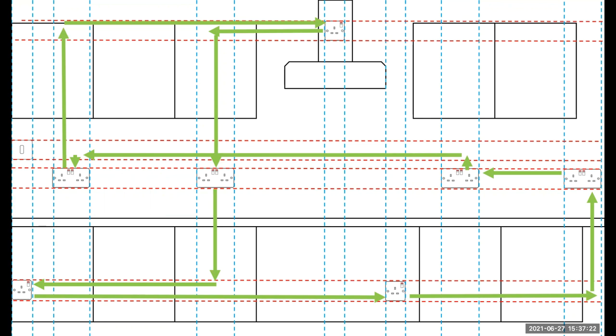And that is exactly what regulation 522.6.202 is for. Now that it's been plastered and decorated, if you hadn't seen them, would you be able to tell me where those cables were? I really don't think you would. I mean, absolutely not. So it completely defeats the objective of that regulation. People just don't stand a chance if you overcomplicate this issue.